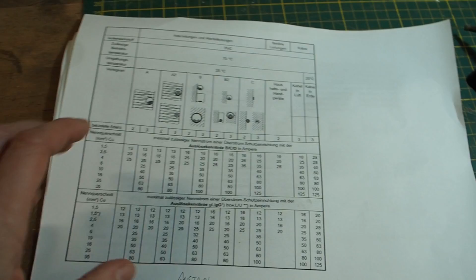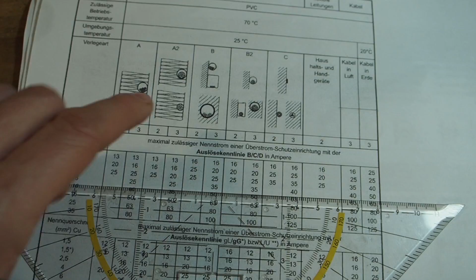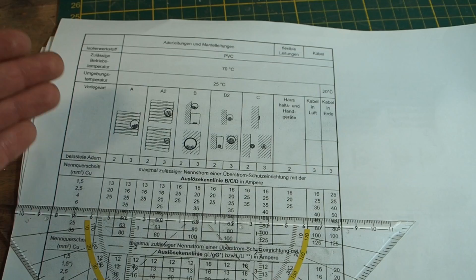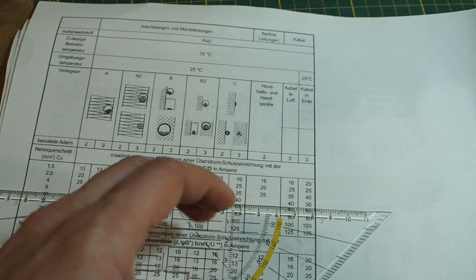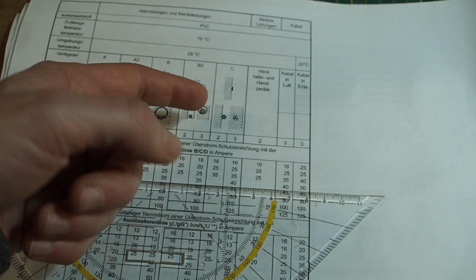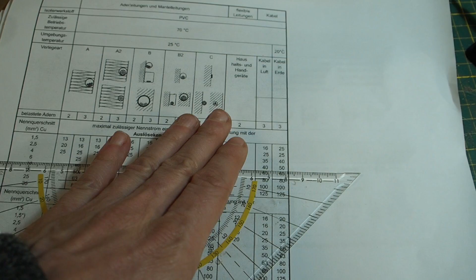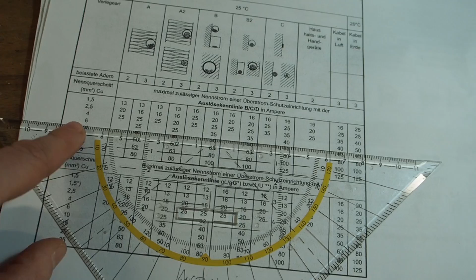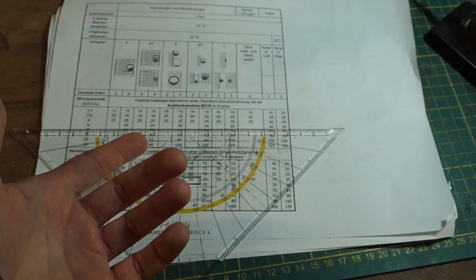Here in Europe we use the metric system, and this is a chart for Austrian electricians showing what size fuse or breaker you can use with a certain wire thickness. There are different columns depending on how the cable is installed. If it's inside a wall, you need much thicker cables because it heats up more easily. But if it's installed in the air, in soil, or only touching one wall, the cable can be thinner for a given breaker size. For a 6 square millimeter cable, the maximum fuse or breaker is 40 amps, and our breaker is 20 amps, so this is more than fine.